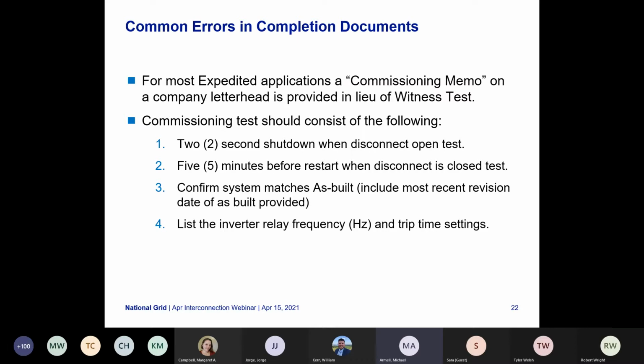The commissioning test should consist of the following: a 2-second shutdown when the disconnect is open test, as well as the 5 minutes before restart when the disconnect is closed test. We confirm the system matches the as-built, include the most recent version, and again, the date of the as-built provided. List the inverter relay frequency and the trip time settings. So that commissioning memo, we want to have all of that contained, and again, the most current version.